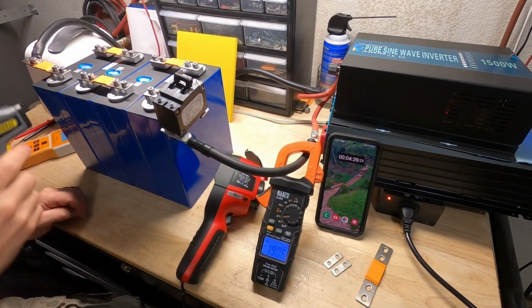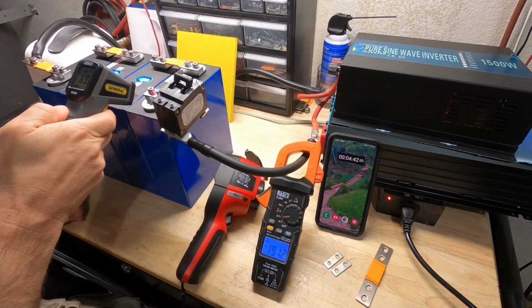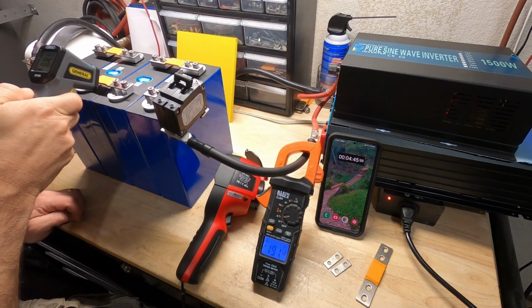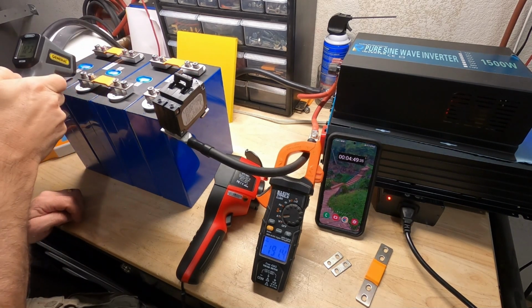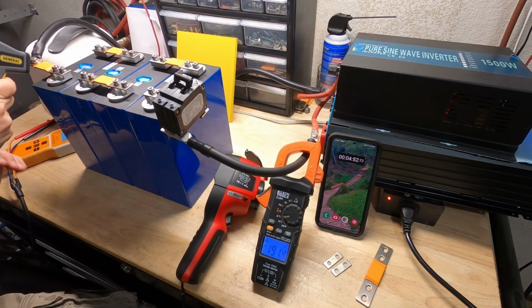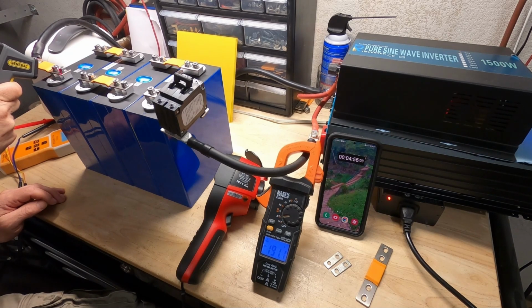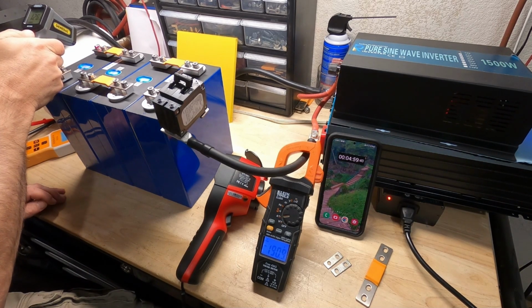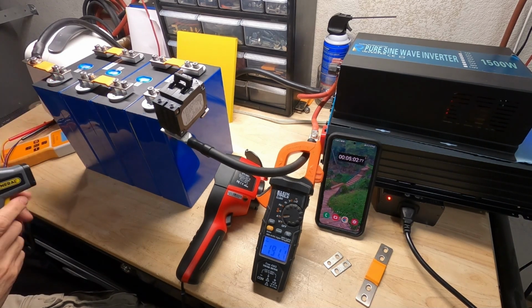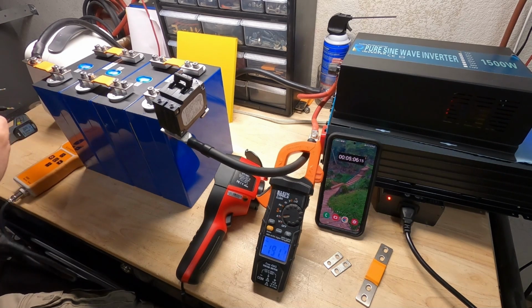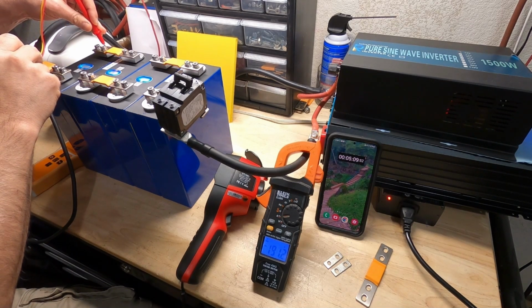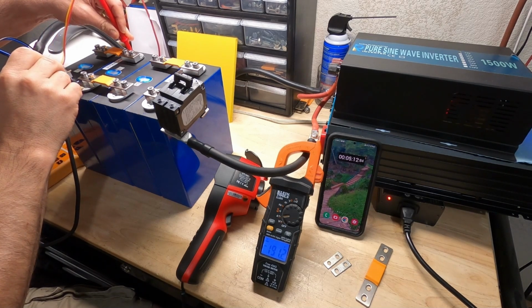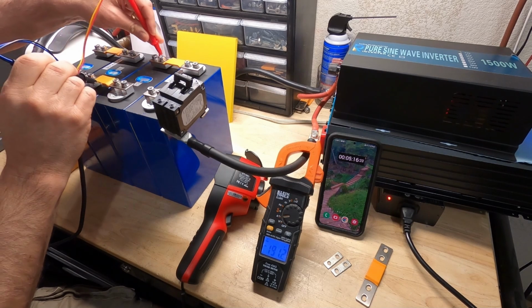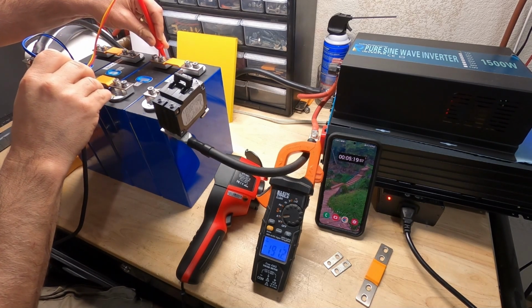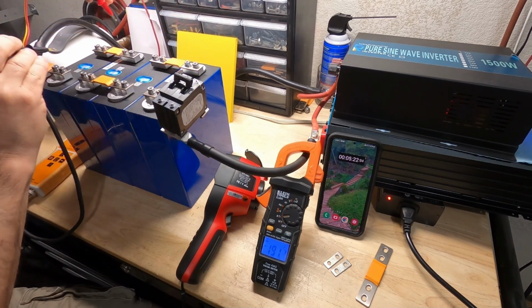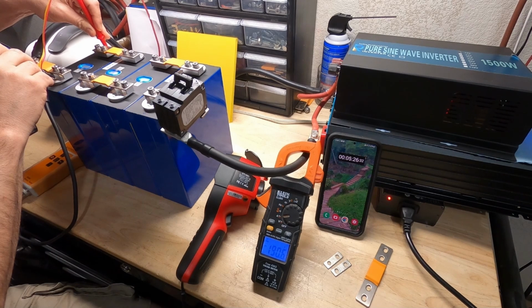Okay, just doing a 5-minute check-in, and I can tell you already just by using this little tester, every terminal right now is at 106 on these 3 cells. But this last cell, 166 degrees on those, 130 degrees about on these terminals. I checked the voltage of the cell for voltage sag, and it's 3.03 volts. That's good. This one's at 3.09. So it's not the cell, it's not voltage sag on the cell. It's a little lower than the others, but that's still fine.